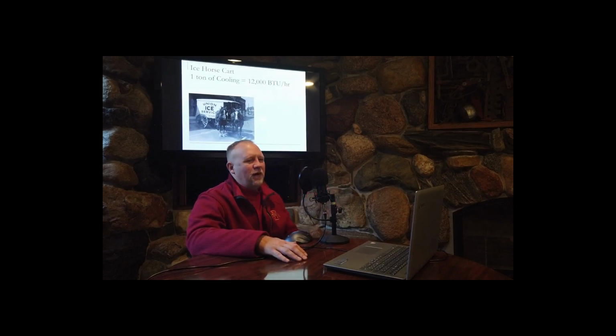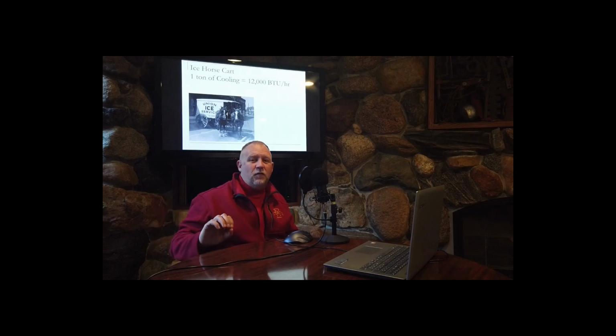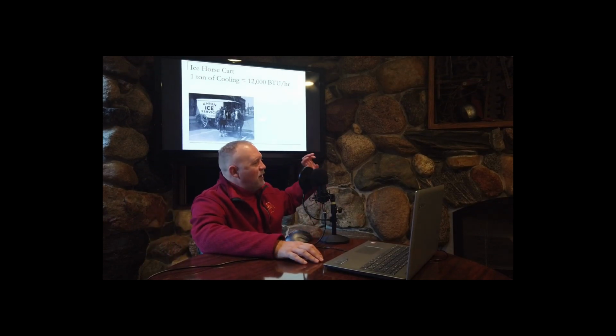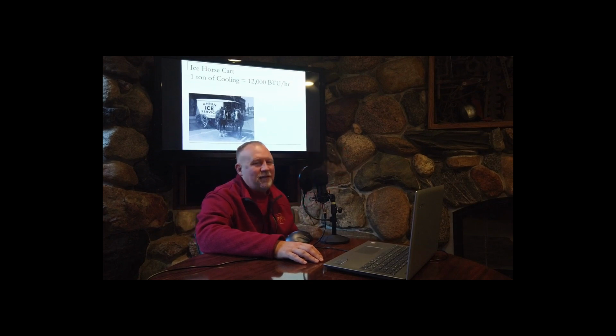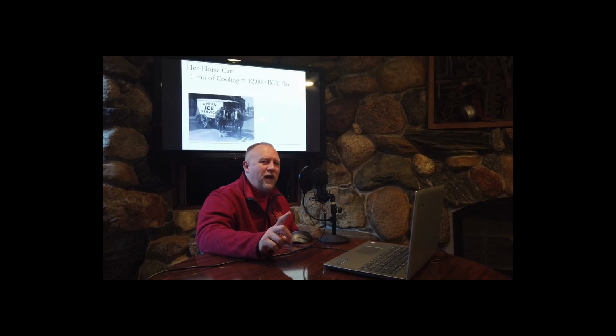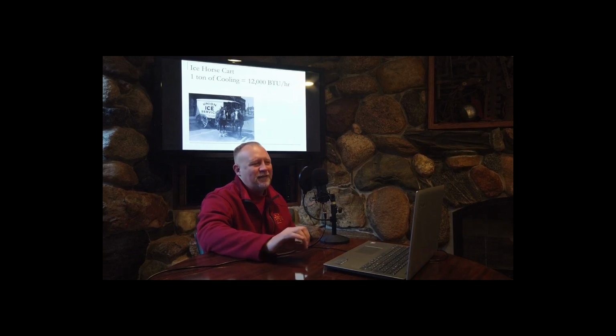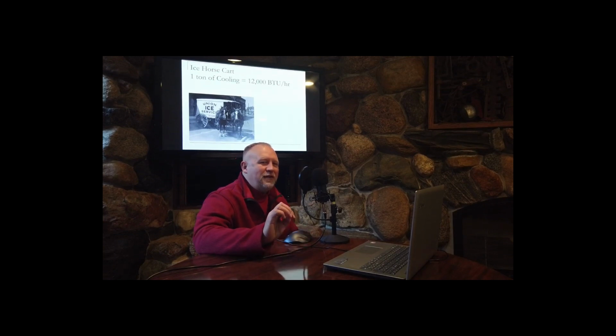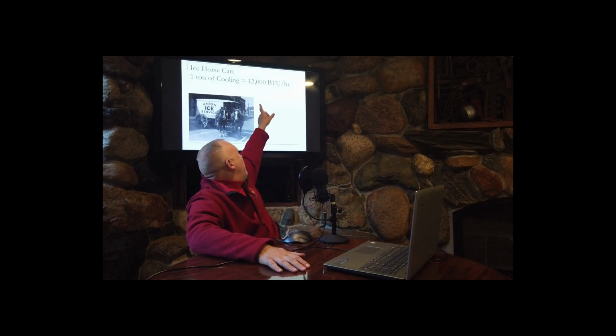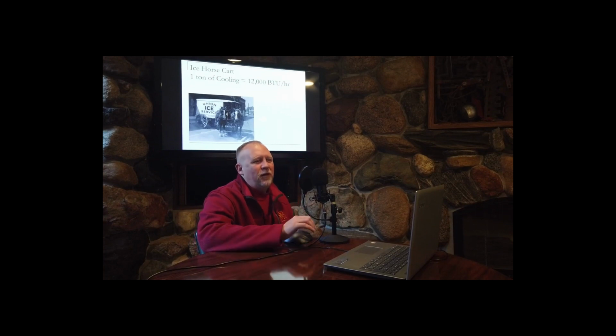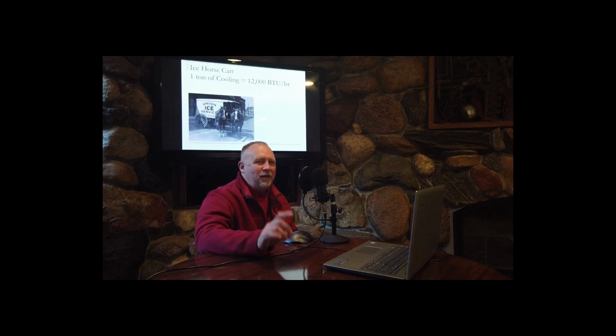That is a 1 ton window air conditioner. That is a 5 ton residential air conditioner. Oh, look at that rooftop air handler that has a 100 ton capacity. Or if we go down to the physical plant for Iowa State, you'll see chillers that have a 1,000 ton capacity or a 3,000 ton capacity. The ton does not refer to the weight of the equipment. A ton refers to 12,000 BTU per hour of cooling capacity, which just happens to be the same cooling capacity that you get when you melt 2,000 pounds of ice in 24 hours.